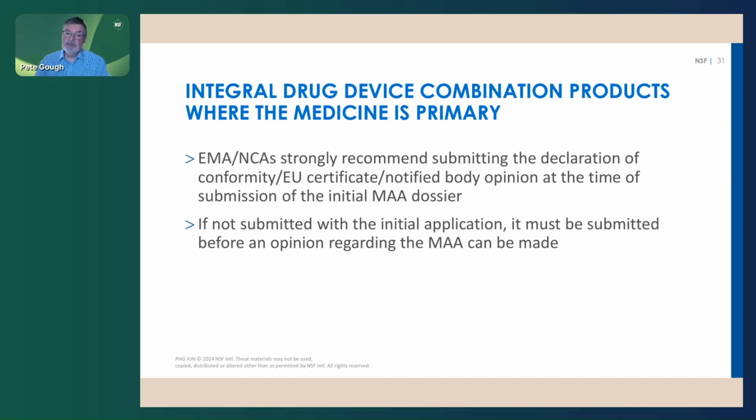If not submitted with the initial application, it obviously must be submitted before any opinion can be given on the marketing authorization application, which can therefore quite significantly delay. If there is a long delay in giving that notified body EU certificate, that conformity assessment, to the competent authority, then that will delay the decision on whether to give you a marketing authorization.